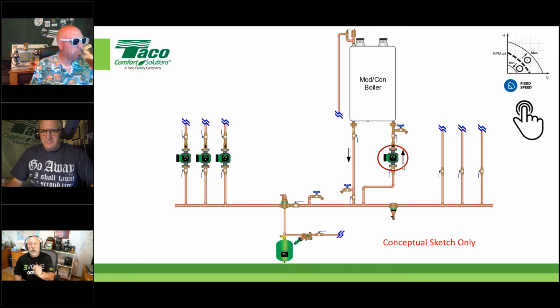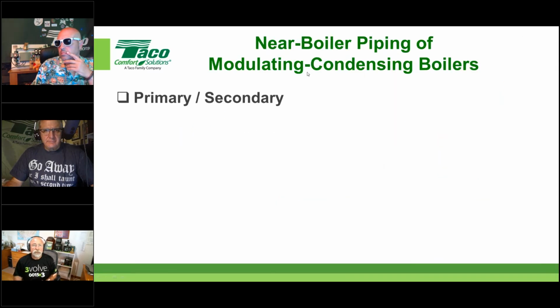Now, when we're talking about the sizing of this pump, it's important to know that not every boiler manufacturer offers that signal, or the circs aren't small enough to have a 0 to 10 volt, then we're going to size this one and run it under a condition we call fixed speed. And if we do that, we just want to make sure that it's sized correctly, because oversizing, again, will lead to poor boiler efficiency. So, near boiler piping, modulating condensing boilers.